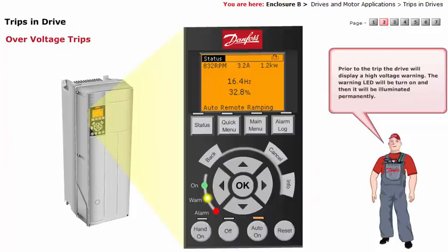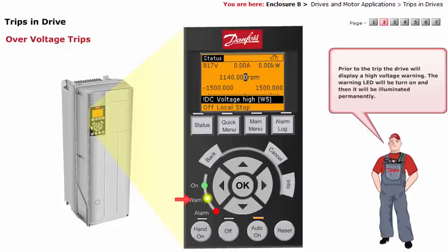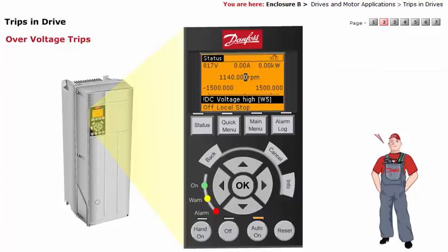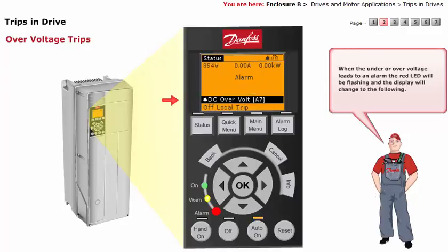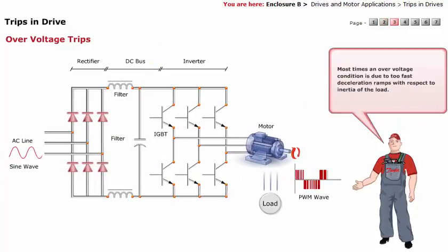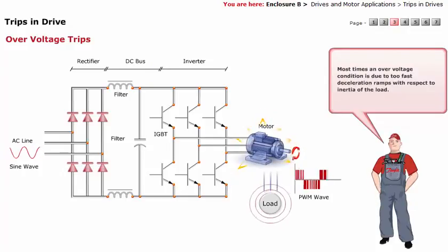Prior to the trip, the drive will display a high-voltage warning. The warning LED will be turned on and illuminated permanently. When under or over-voltage leads to an alarm, the red LED will be flashing and the display will change accordingly. Most times, an over-voltage condition is due to too fast deceleration ramps with respect to the inertia of the load. During deceleration, the inertia of the system acts to sustain the running speed.